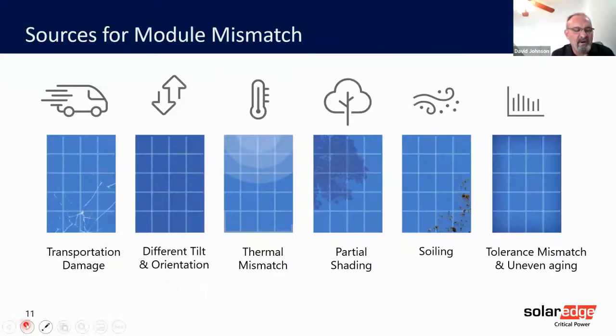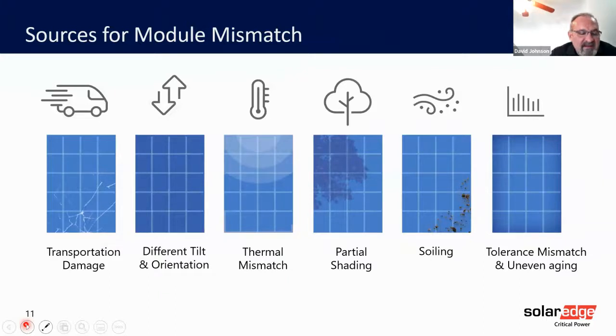What else can cause module mismatch? Many reasons. Some can't even be seen, like microcracks. Some are very visible, like shading. Some can be expected, like obstacles on the roof. Some cannot, like dirt and bird soiling. Some are permanent, like damage to the module, and some are transient, like cloud shading.